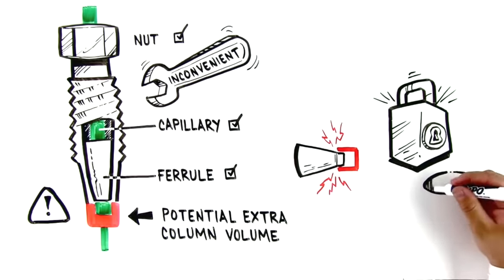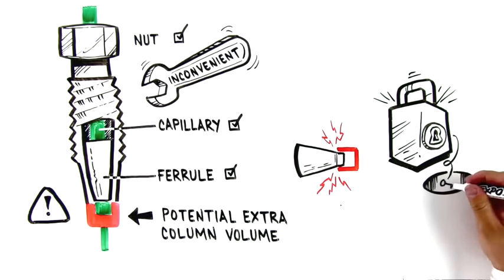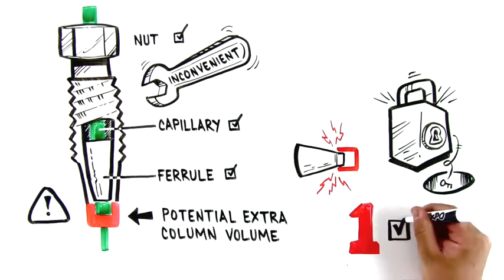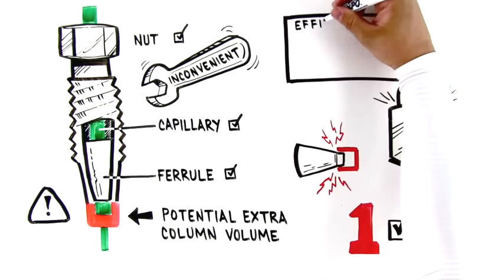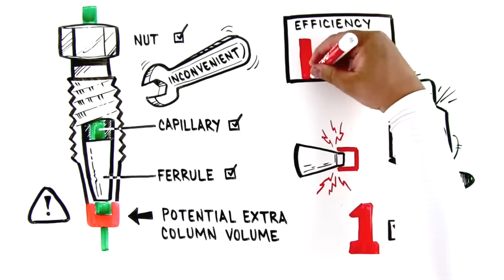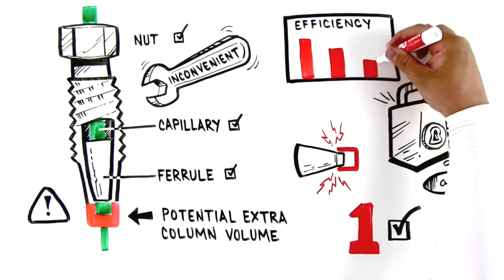A ferrule-based fitting therefore only fits best on exactly the column or valve it's first connected to. This bears the inherent risk of unwanted void volumes in the fluidics, which will immediately negatively impact the efficiency.